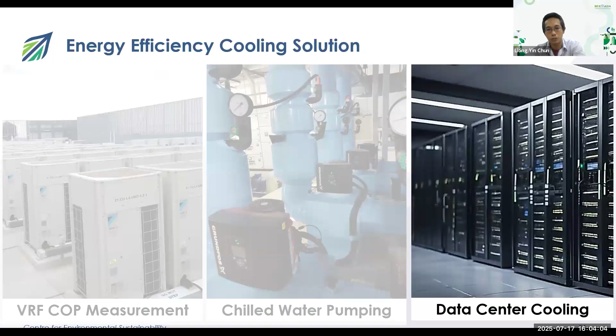In Singapore, mostly we are still doing the air cool system, where we have a CRAC unit, which is basically an aircon. It pumps cold air to the raised floor, and you have many racks of servers lying on the data center floor. If someone is using a particular rack, the damper in front of it opens to allow cold air to come out, and fans inside the rack suck in the cold air to cool down the server. After the cool air passes through the server and becomes hot or warm air, it goes through the hot aisle and back to the CRAC unit to be cooled down again. This is basically just an aircon, so with it you definitely need a chiller and a cooling tower — a whole set of aircon systems to support the air cool system for the data center.